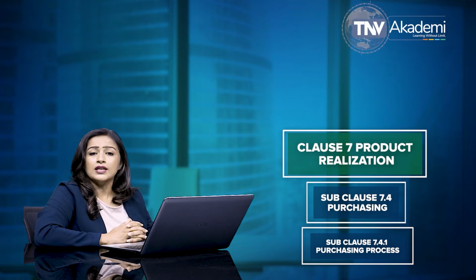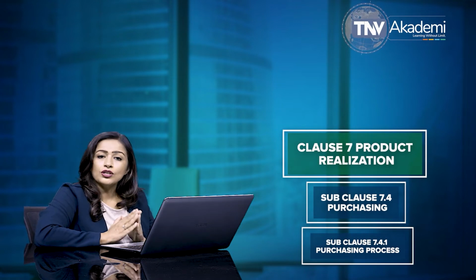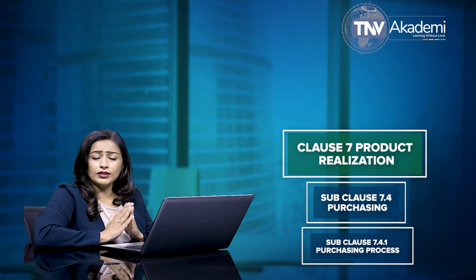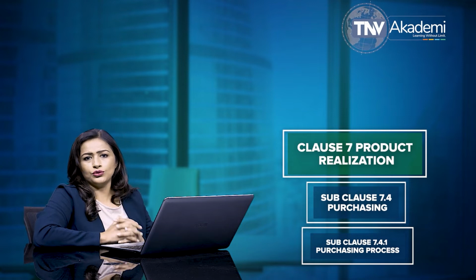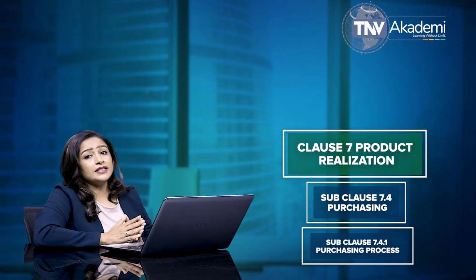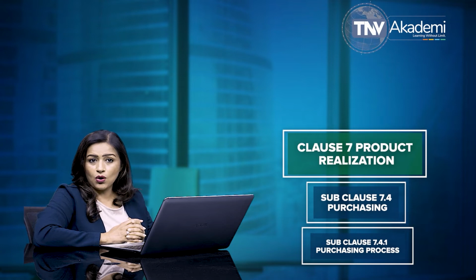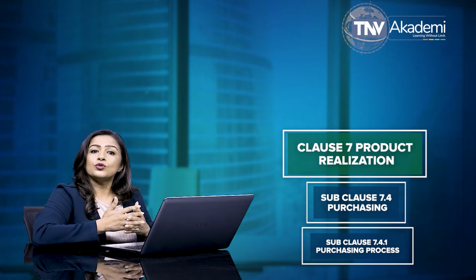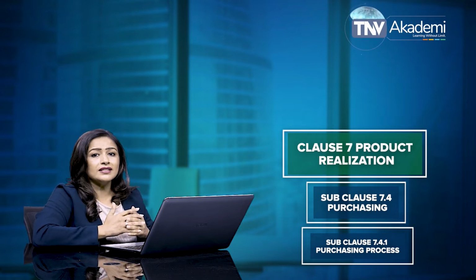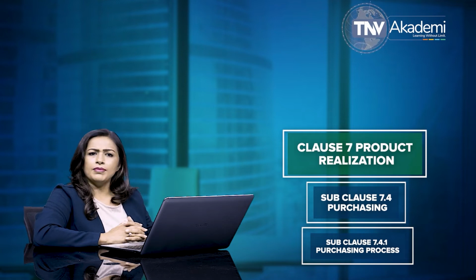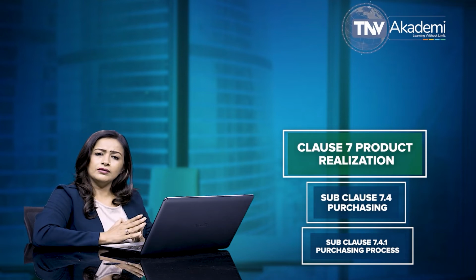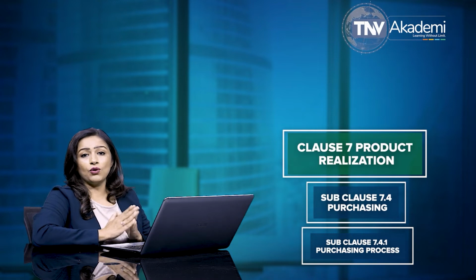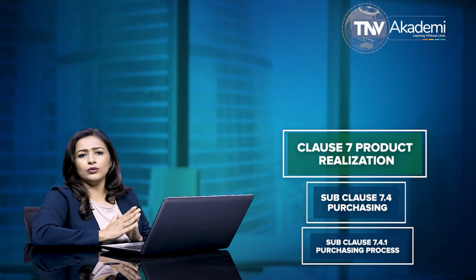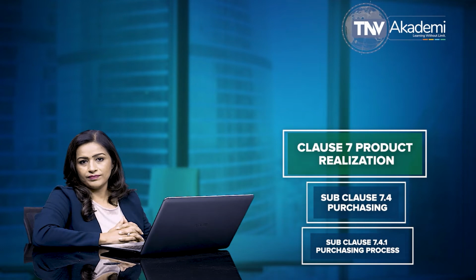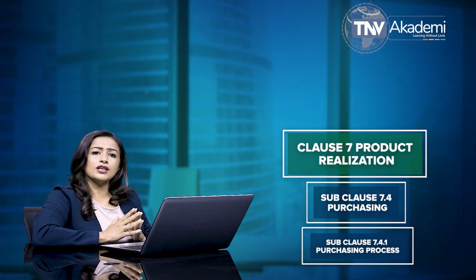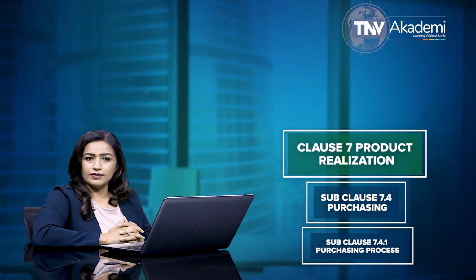As per this clause, the organization is required to establish criteria for the evaluation and selection of suppliers. The criteria must be based on the supplier's ability to provide product that meets the organization's requirements, based on the performance of the supplier, based on the effect of the purchased product on the quality of the medical device, proportionate to the risk associated with the medical device.